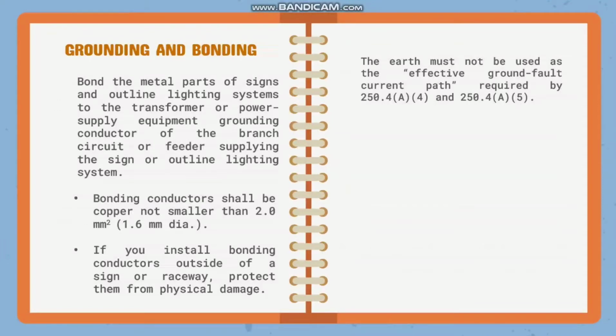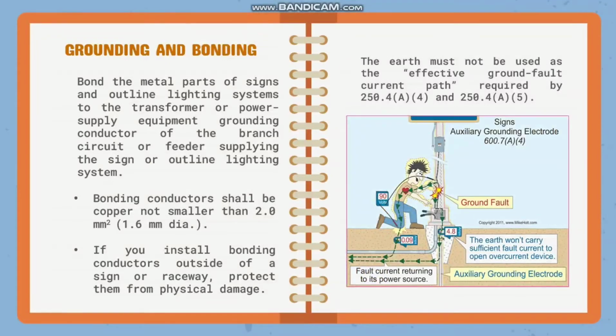So, bakit nga ba di pwedeng gamitin yung earth as an effective ground fault current path? So, the reason for that is because the contact resistance of your grounding electrode to the earth is high, and very little ground fault current returns to the electrical supply source via the earth. So, the result, the circuit overcurrent device won't open and clear a ground fault. Therefore, metal parts will remain energized with dangerous voltage. So, as the figure shows, so yun, na yung lalaki is na-ground siya.